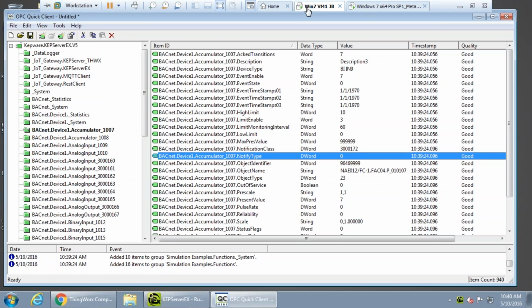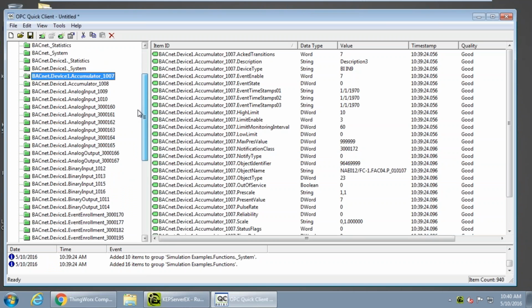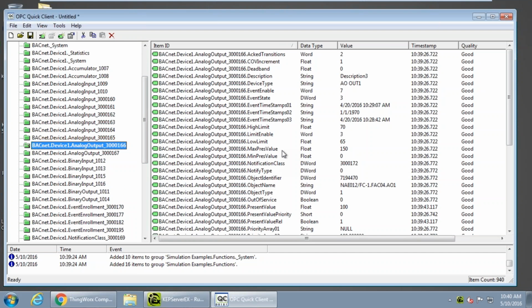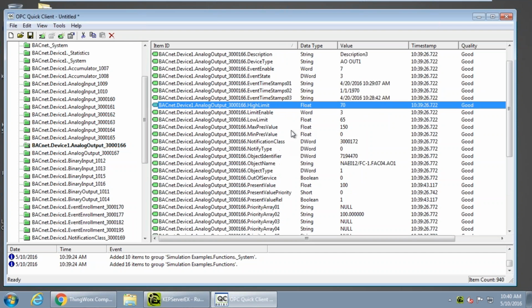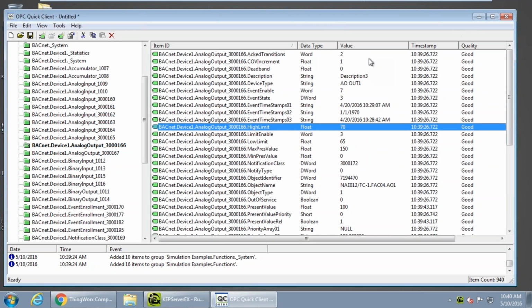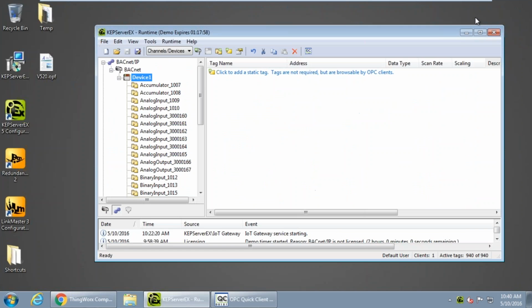So that analog object, or analog output, which we see represented here, now has these different alarms that will actually allow us to gather alarm data from there. And so instead of constantly polling that device to see if the data has changed or if it's in a fault state, you can conserve network bandwidth because we're now just sitting there waiting for the intrinsic alarm to notify us that there's been a change. So we won't be polling if we're looking for those alarms.